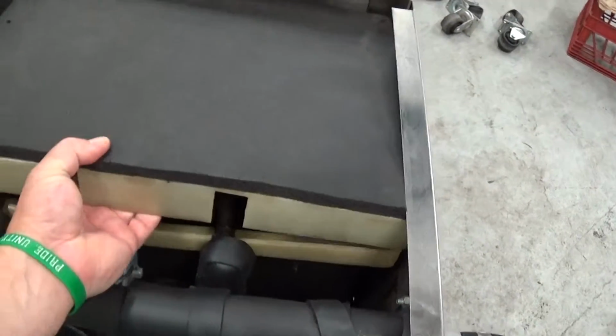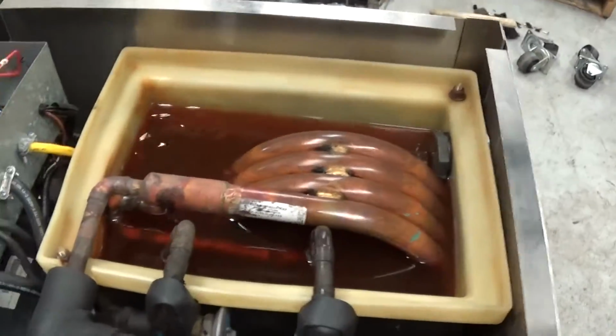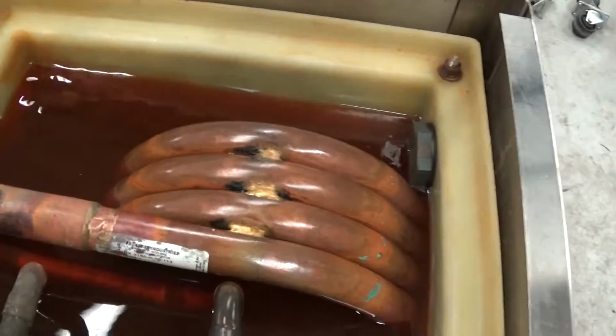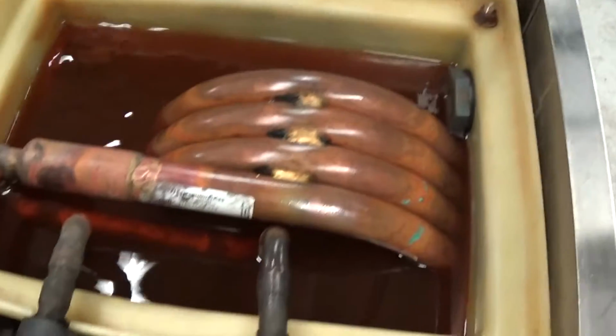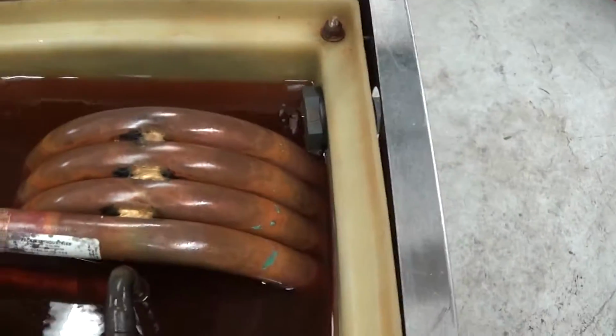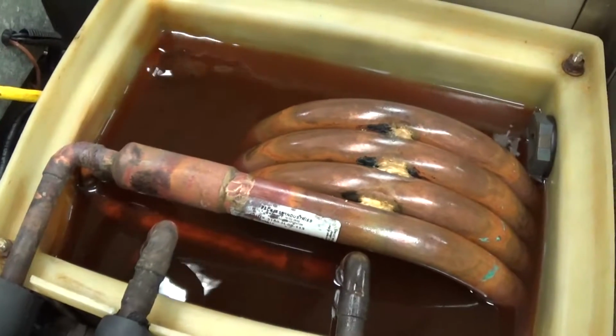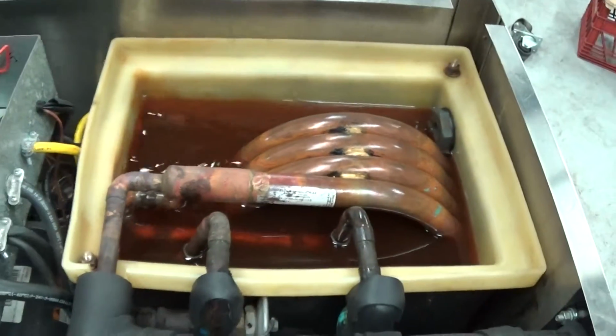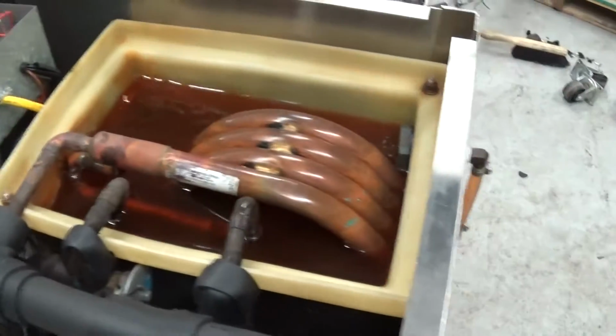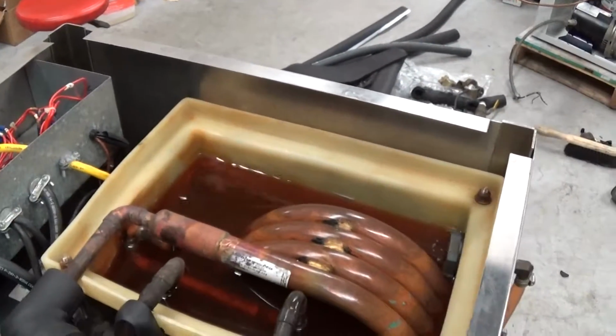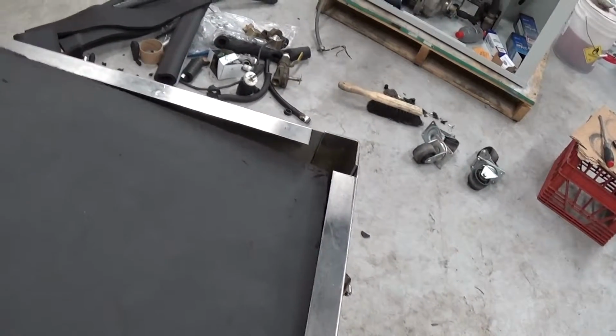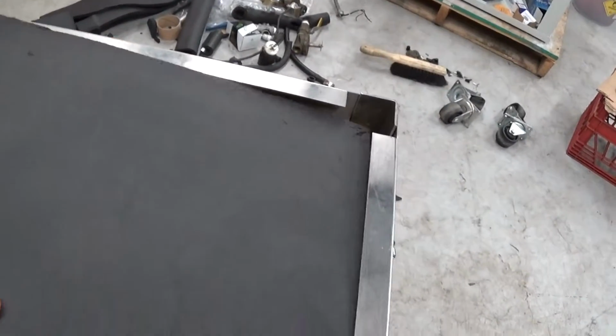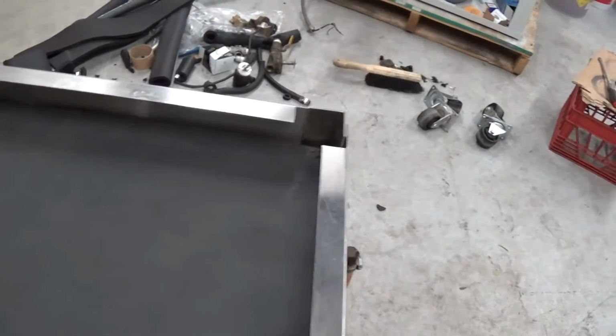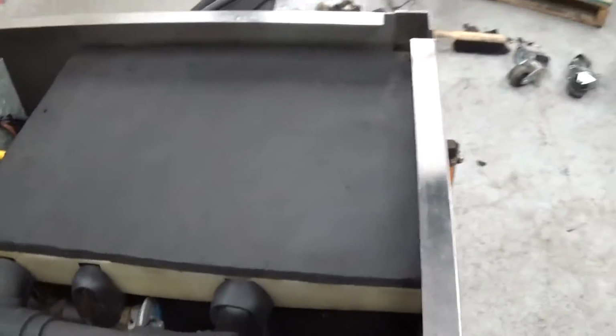This type of unit has a coil and tank exchanger. So the refrigerant and the fluid go through this coil here. We actually like these on smaller chillers. Simple, and you get some really good heat transfer. And you still should have a Y strainer or some type of filter on your process water.